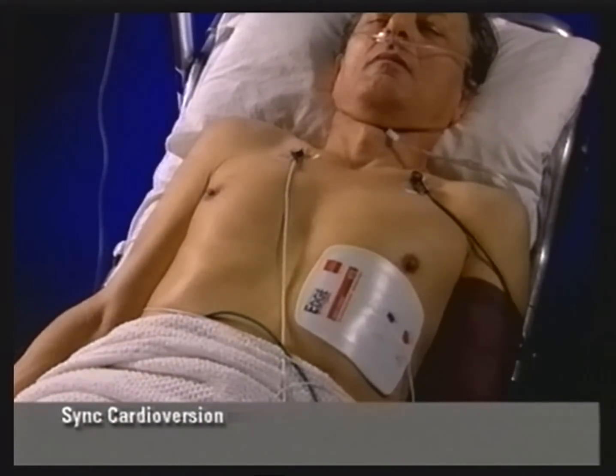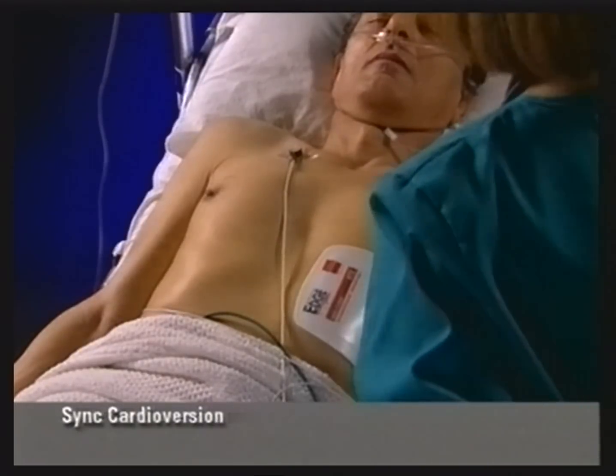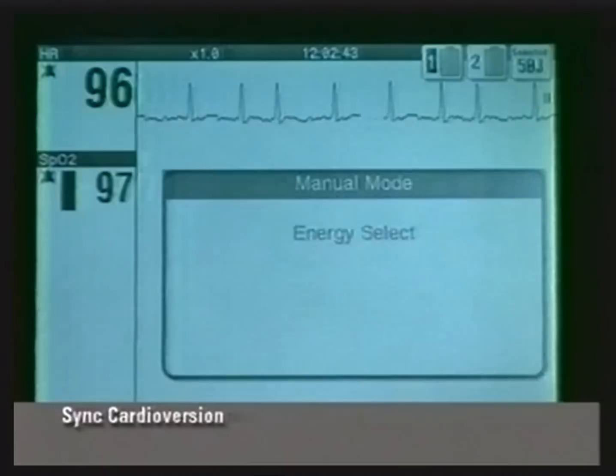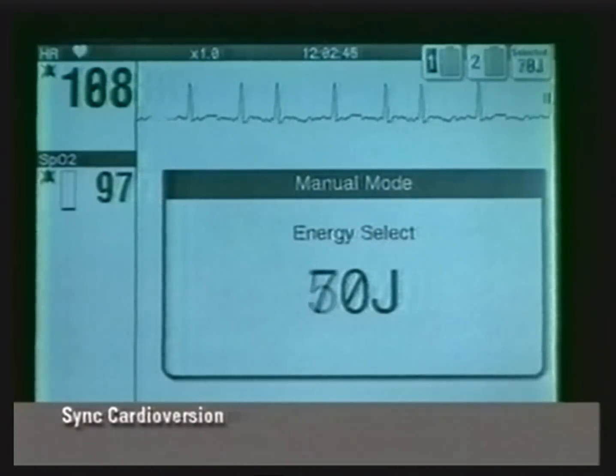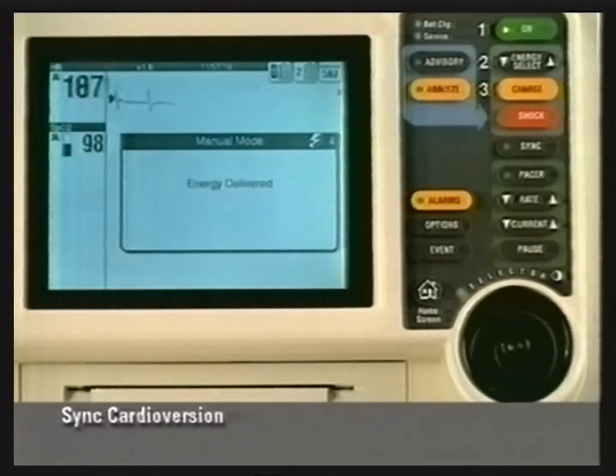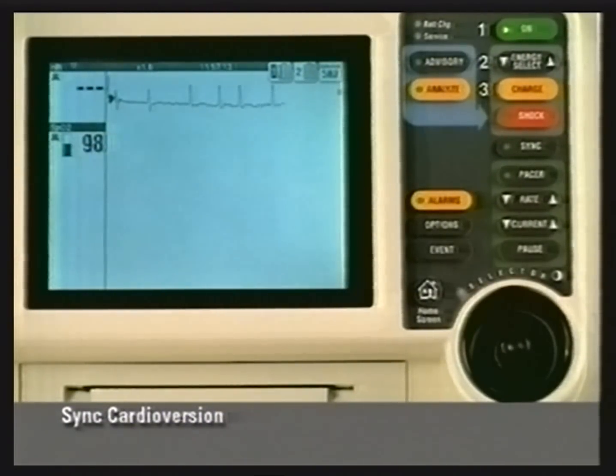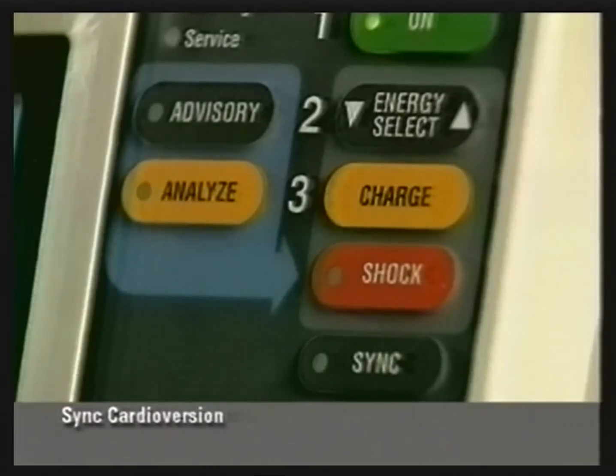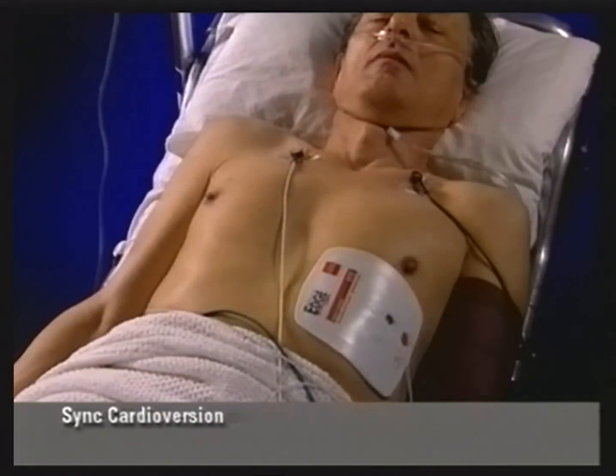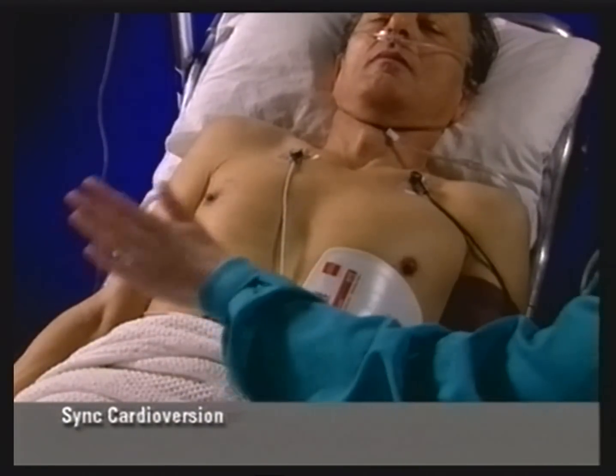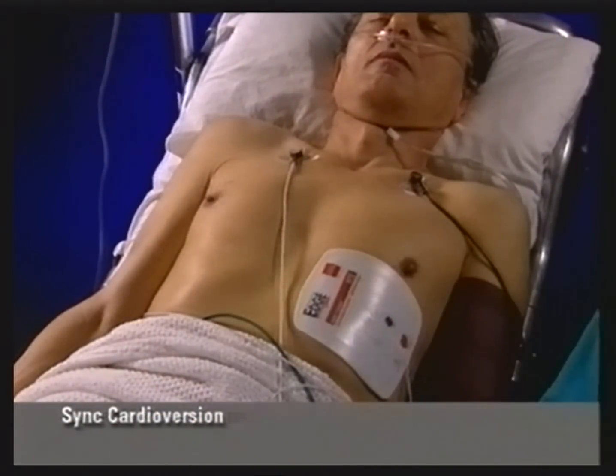Assess the patient and the ECG rhythm after the shock. If the arrhythmia persists, select energy according to your local protocol. If your defibrillator is configured to automatically return to asynchronous mode following a shock, press sync again. Repeat the charging and discharging sequence. I'm clear, you're clear. We're all clear.